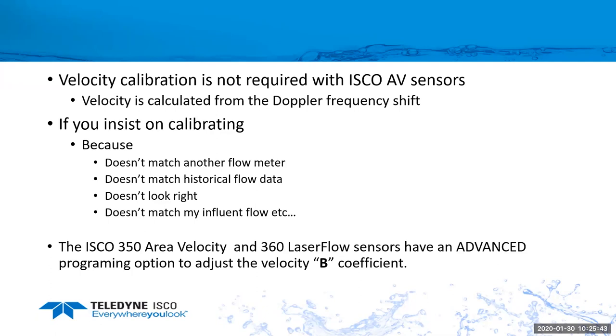But if you insist on calibrating because it doesn't match another flow meter or historical data, it's one of my favorites when they say for 5 years I've been getting the exact same flow rate and it doesn't match that. I find that hard to believe sometimes. Or if they just say the flow rate doesn't look right, or it doesn't match my influent flow.